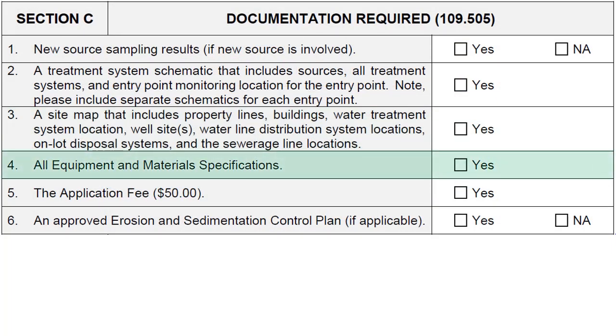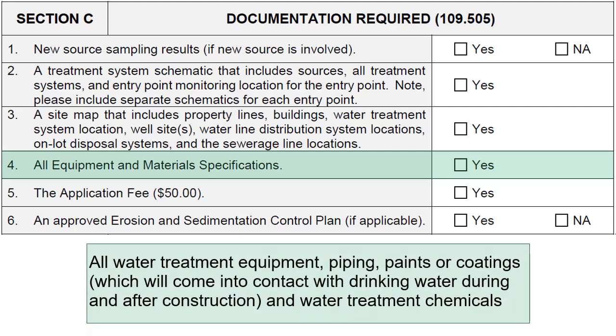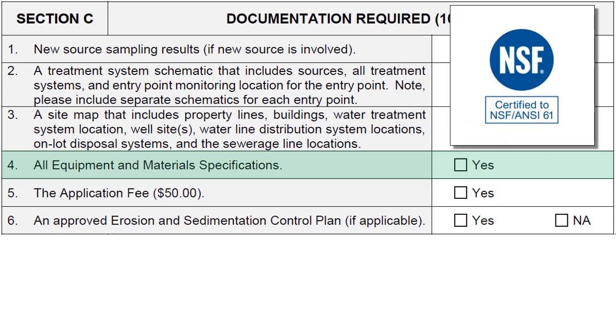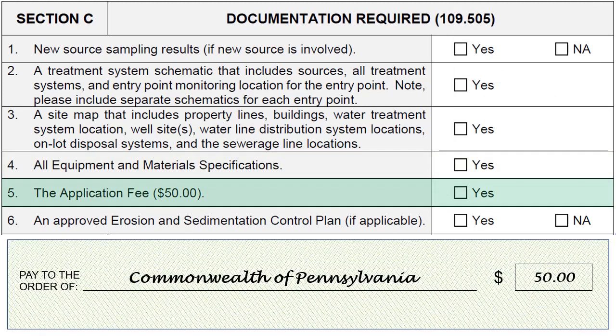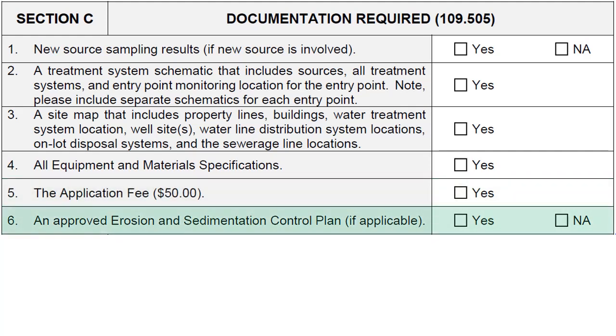For equipment and material specifications, include all specifications for all water treatment equipment, piping, paints or coatings which will come into contact with drinking water during and after construction, and water treatment chemicals. This information should be readily available from the manufacturer or found on their website. All materials that come into contact with or affect the quality of the water must be acceptable to the department. Materials which are certified for conformance with ANSI NSF Standard 61 are deemed acceptable. An application fee of $50 made out to the Commonwealth of Pennsylvania must accompany each application. The applicant shall also include an approved erosion and sedimentation control plan when earth moving activities are involved.